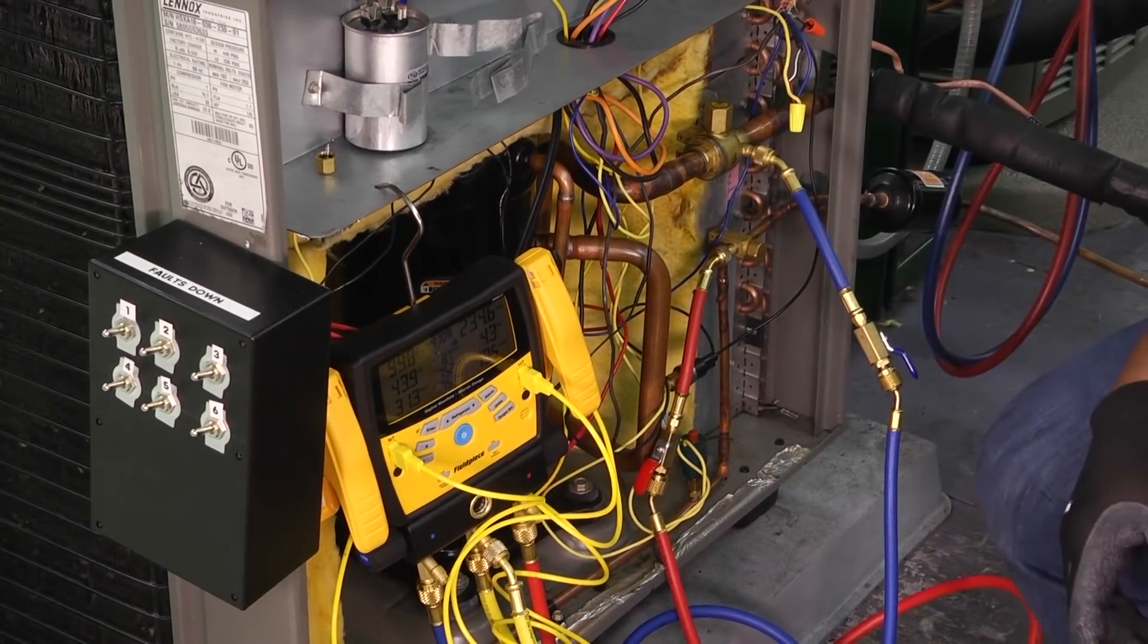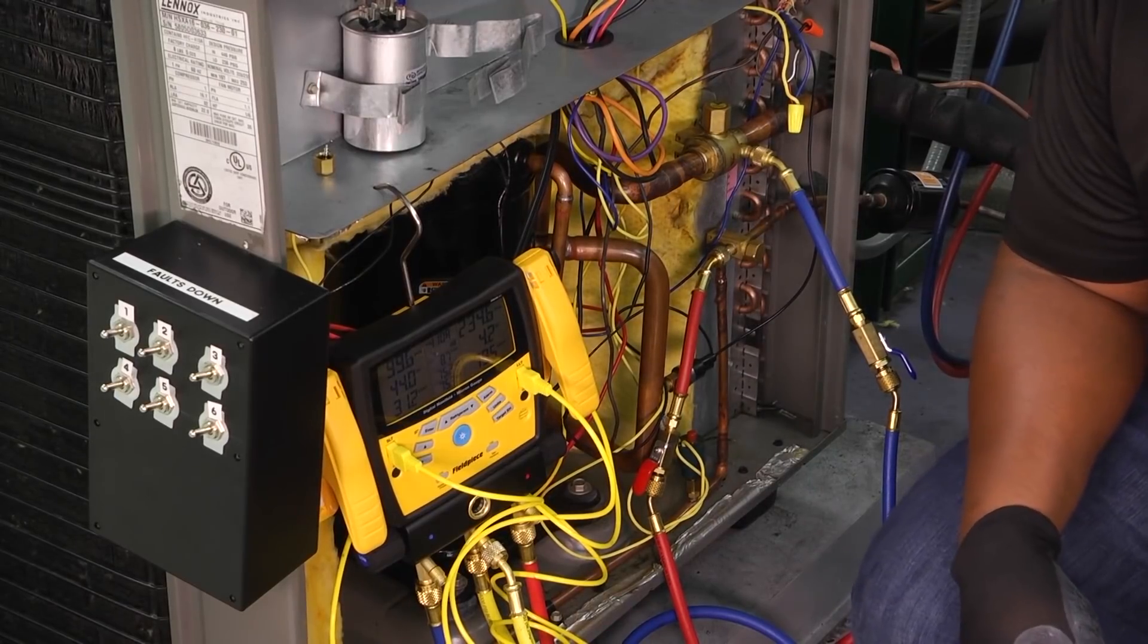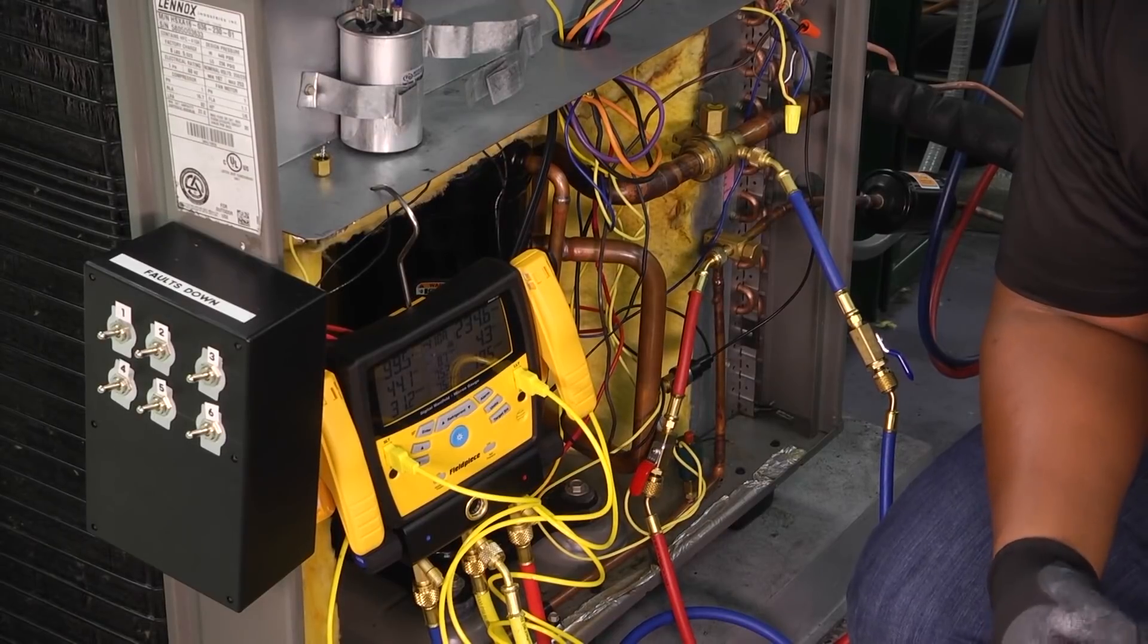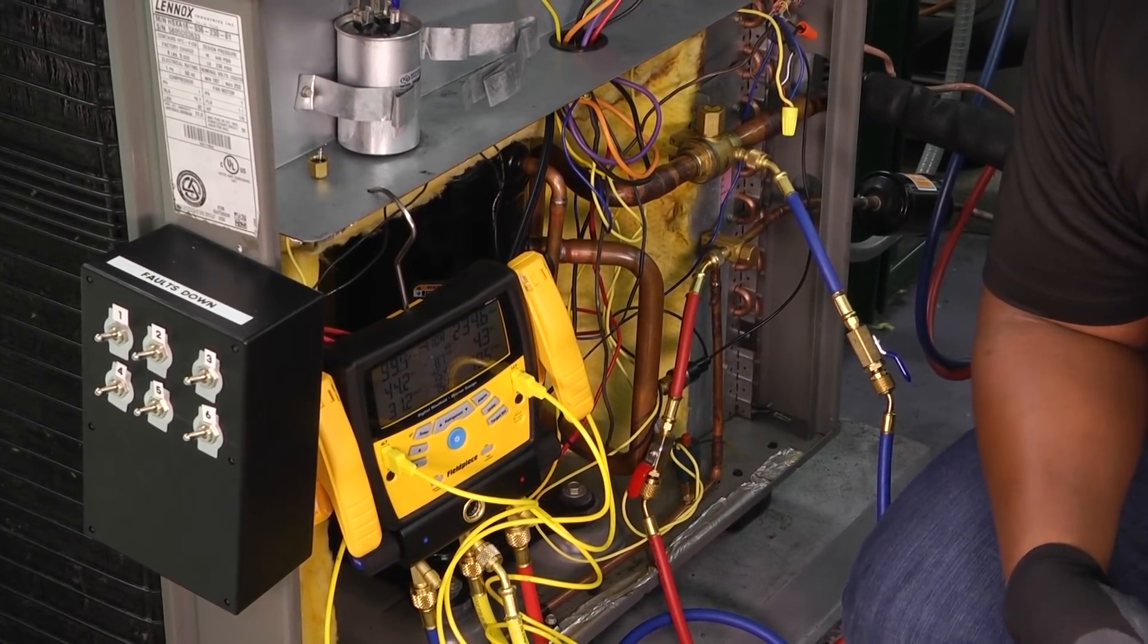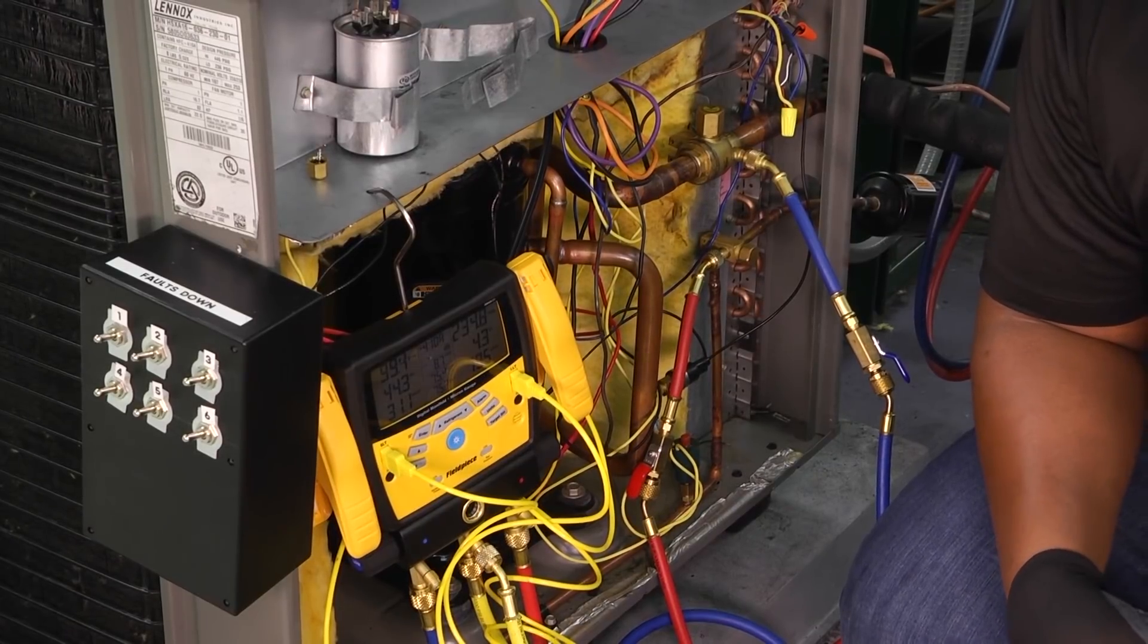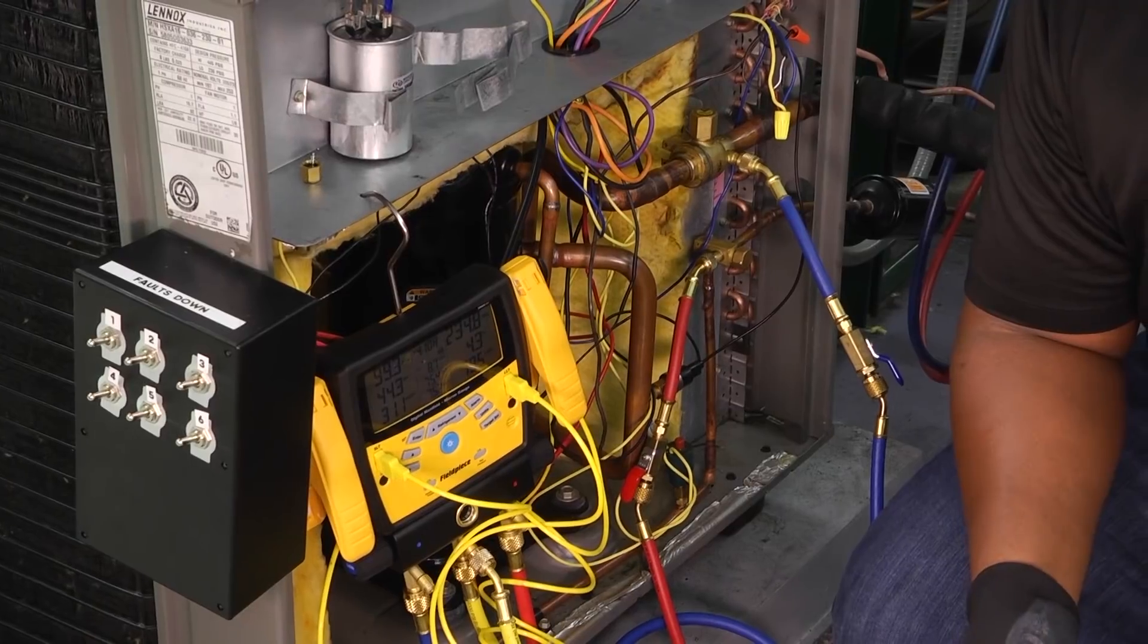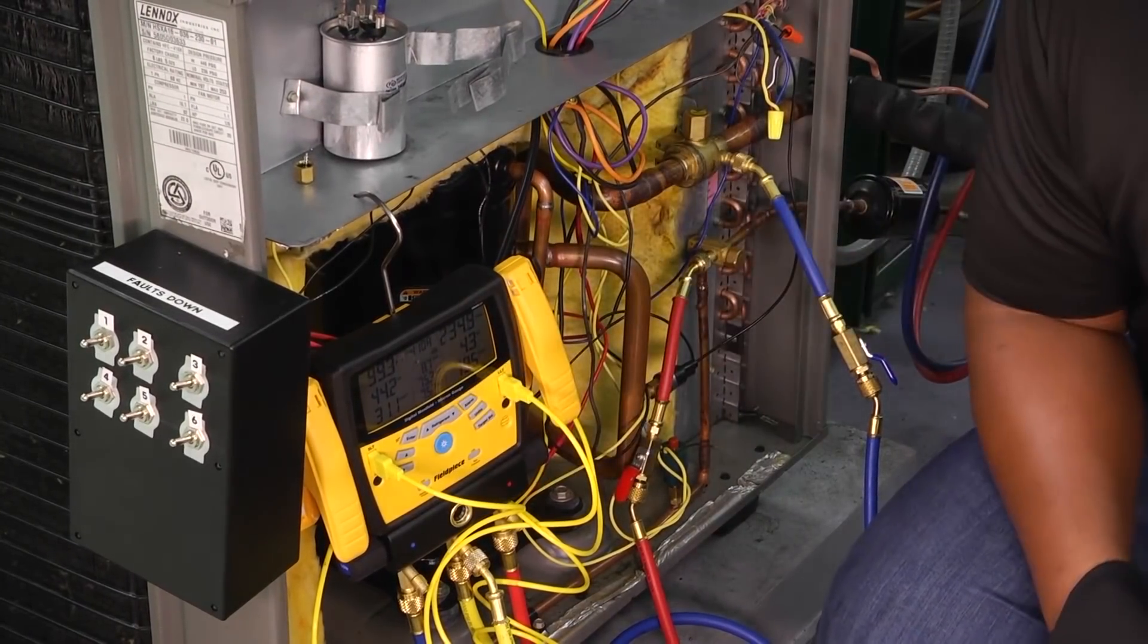The very first thing that we need to do is we need to determine what type of metering device we have. If we have a TXV or whether or not our metering device is a fixed orifice, that's going to be very important at the number that is most important to us in charging. For example, if we have a fixed orifice metering device, we're going to charge looking at our superheat number.